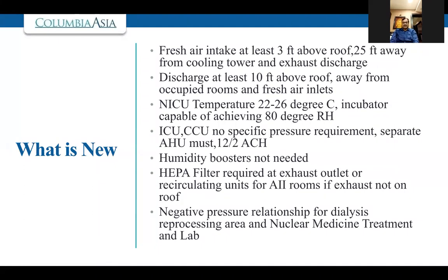So what is new? This is important, because generally there is a lot of misunderstanding about this. Fresh air intake for all AHUs, mind you, again, for all AHUs which are in critical areas, for example ICUs, operation theaters, endoscopy, should be at least 3 feet above the roof and 25 feet away from cooling towers and exhaust discharges. Many times the isolation room exhaust is very close to the fresh air intake of the operation theatre, which is not accepted, which is not correct, because it will lead directly to germ deposition. And the discharge or exhaust should be 10 feet above the roof so that there is no coming back of that discharge to the facility.